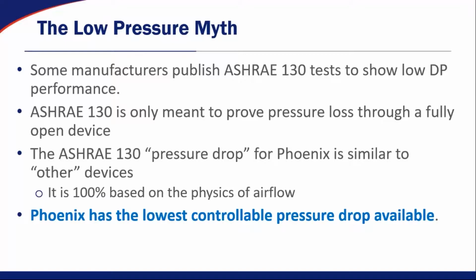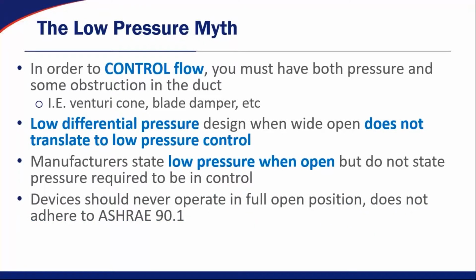So what we claim as Phoenix Controls, and what we've proven time and again, is that Phoenix has the lowest controllable pressure drop available. And that means when we say we're plus or minus 5% across the full flow range and pressure range of the valve, we have the lowest pressure drop to be able to stay at that plus or minus 5% accuracy. It doesn't matter if a device flows air when it's fully open. If you don't have some obstruction inside the ductwork to control the flow, you're not really controlling anything. So it just basically means ASHRAE 130, I want to know what flow I can get at a given pressure. I fail my device open, I measure my flow, and that's what I put on my data sheet.